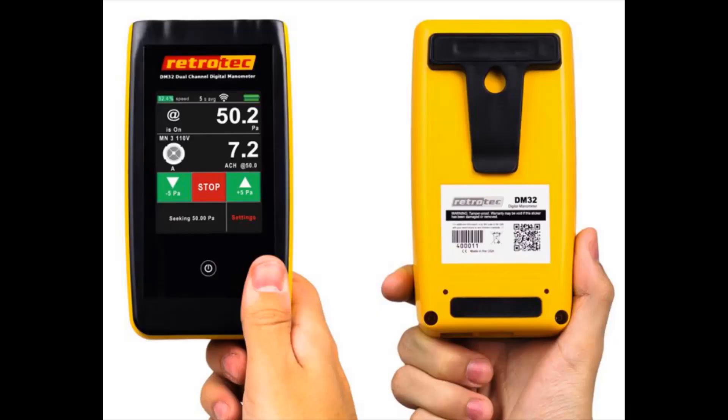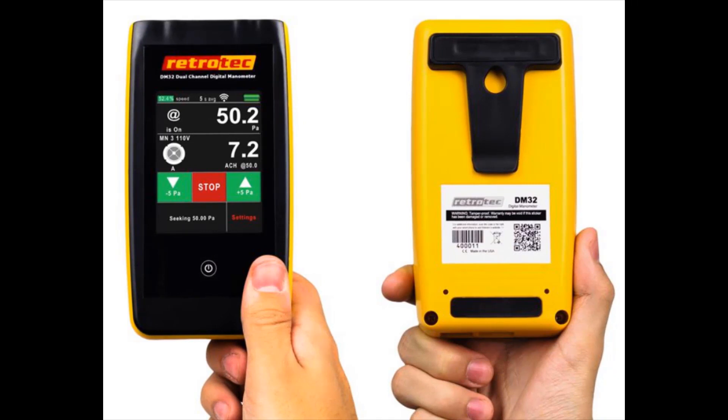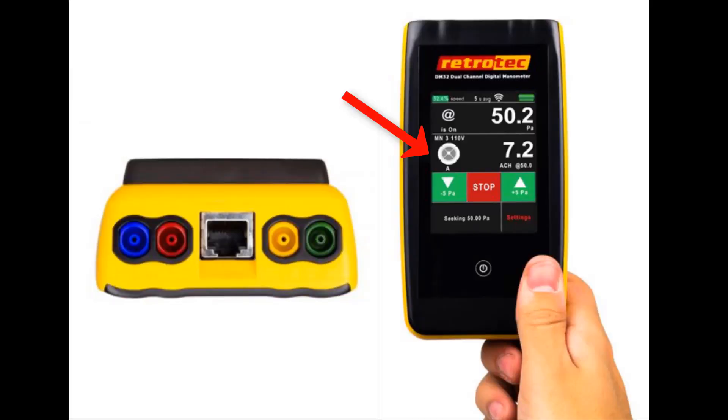The DM32 doesn't need this additional tube connected because the gauge is smart enough to know to cancel out that pressure induced by the blower door. When the blue input port on the A channel feels a positive pressure while a blower door is selected, it will mathematically remove that additional pressure from the equation.